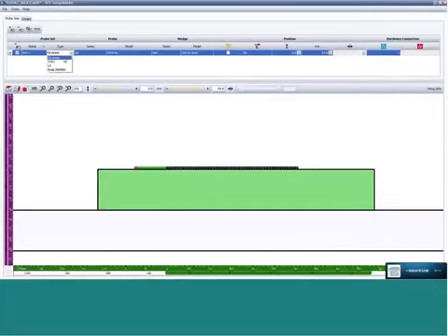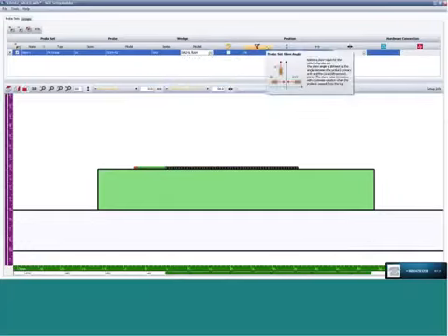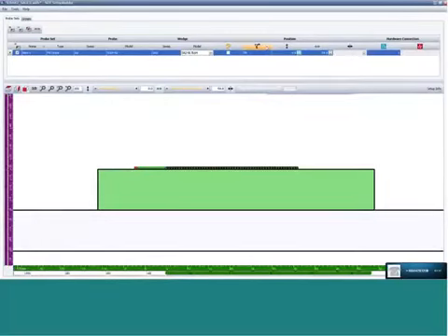we select from a PA linear, TOFD, a UT probe, or a dual matrix array. The probe series and model is entered. The associated wedge series and model is entered. The position is relevant to the beam angle.